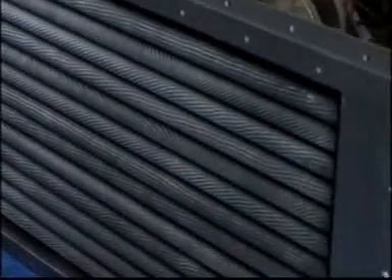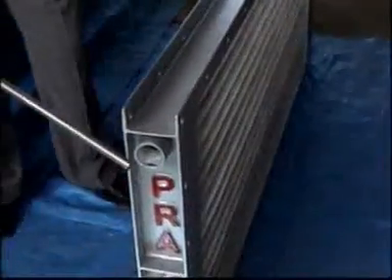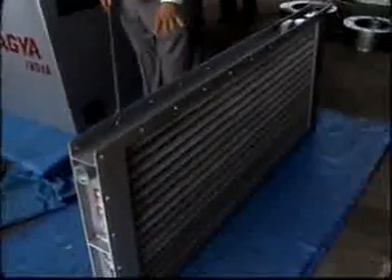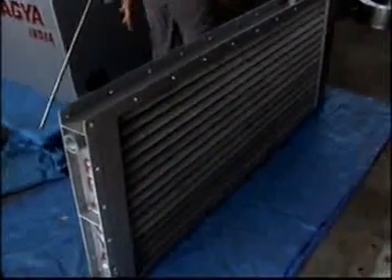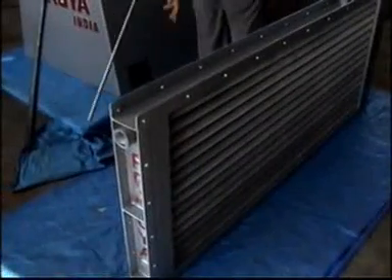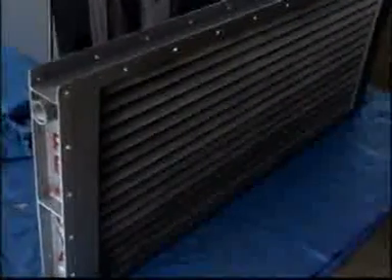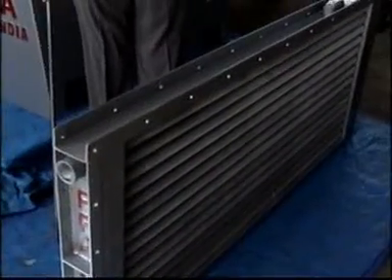This is one of the typical examples. The reverse way, you can also use it for cooling the oil. Suppose there is hot oil, hot hydraulic oil or vegetable oil, you just send the oil from this port and get the cool oil from that port, and all the heat of the oil will be carried away by two blowers. One is here, an FD blower which sends the cold air, and on the other side you get the hot air, and the oil is cool. So this is the reverse application of this radiator.